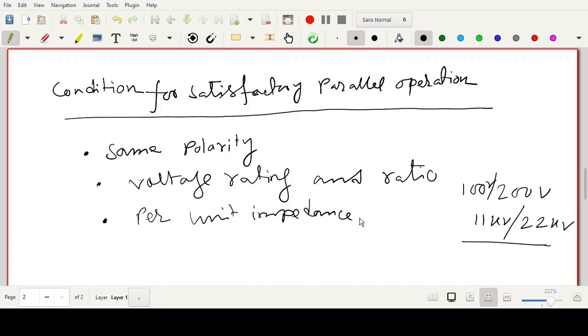So that their load sharing will be according to their kVA rating. The kVA rating is more, it will take more load. kVA rating is less means it will take less load. So this condition should be satisfied. Per unit impedance should be same for all the transformers. Per unit impedance means this impedance divided by the kVA of the transformer.